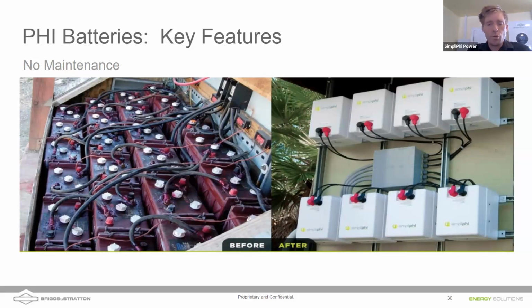I hope I answered those questions. One more thing to Paul - typically on our charge and discharge cycles, our chief engineer tells us that the batteries are normally in that 25 to 40 degree Celsius optimal temperature range fairly quickly, so it shouldn't be charging at 20 amps for a long time.